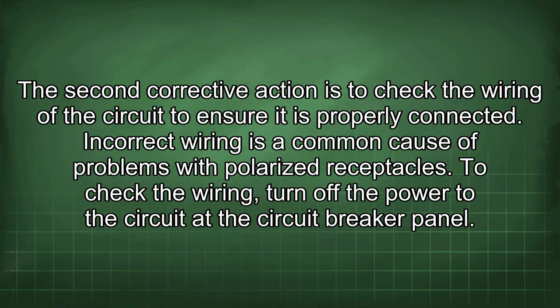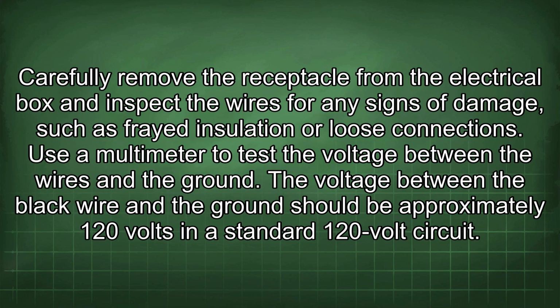The second corrective action is to check the wiring of the circuit to ensure it is properly connected. Incorrect wiring is a common cause of problems with polarized receptacles. To check the wiring, turn off the power to the circuit at the circuit breaker panel. Carefully remove the receptacle from the electrical box and inspect the wires for any signs of damage, such as frayed insulation or loose connections. Use a multimeter to test the voltage between the wires and the ground.